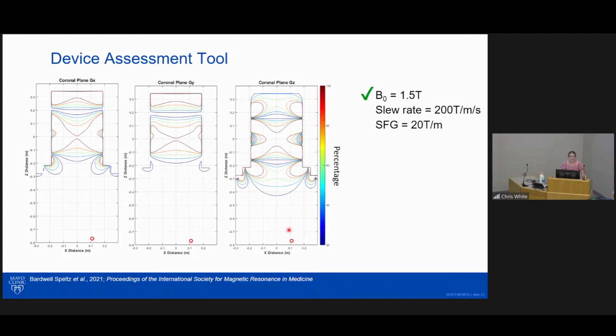But if you didn't have the lines, didn't have the device, and the physicist is like, yeah, we're fine. Yes, that's a good question. If we didn't have this specific device assessment tool, manufacturers give you, for each of their scanners, field maps of their B0 field and their spatial field gradient. So you could look at those maps and compare, type of thing. Yes, overlap. Makes total sense.